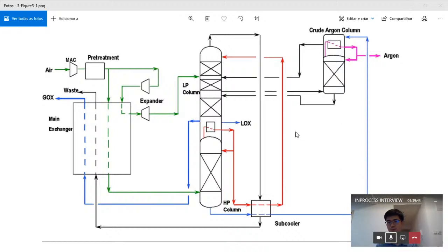And about operations, do you have experience with operations? Can you give me some advice for those who operate cryogenic plants? Sure. I'm focused on design, but I have traveled to a lot of plants for commissioning, startup, or optimization. My advice for operation is that first priority, you need to care about safety-related shutdown set points and critical parameters like the main condenser level and purity, such as CO2 or hydrocarbon content.